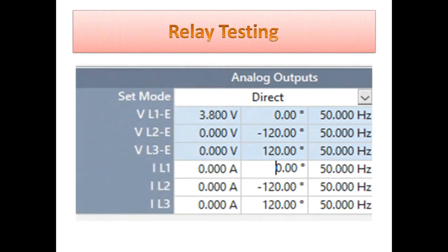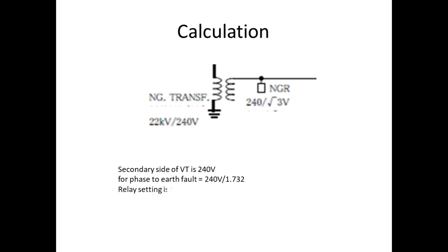Now we will see how to test this 95% earth fault protection. Before going to testing, we have to see the NGT VT ratio. If you see it, it has 22 kV over 240 volts.